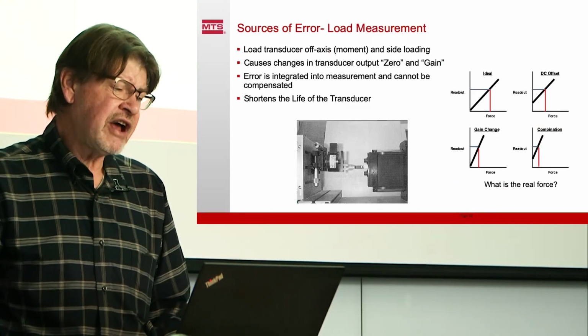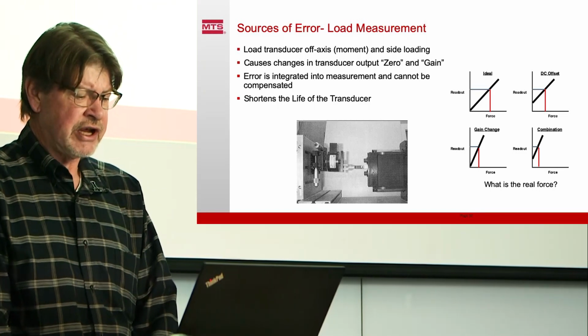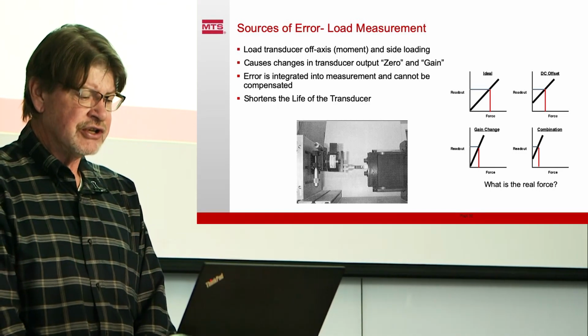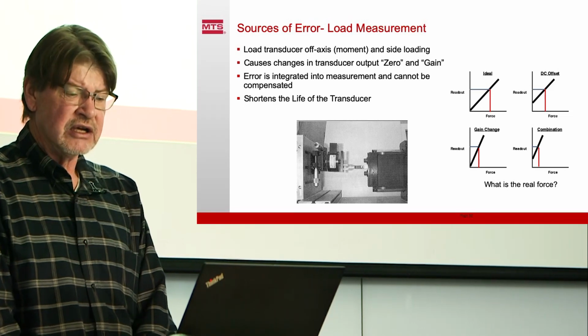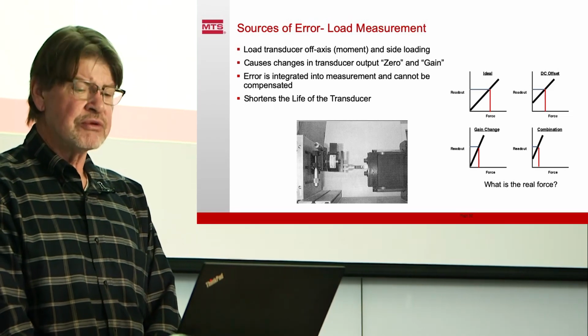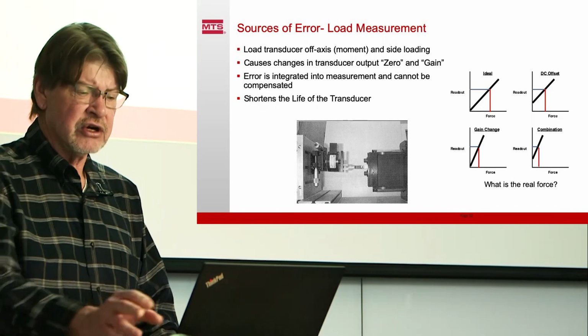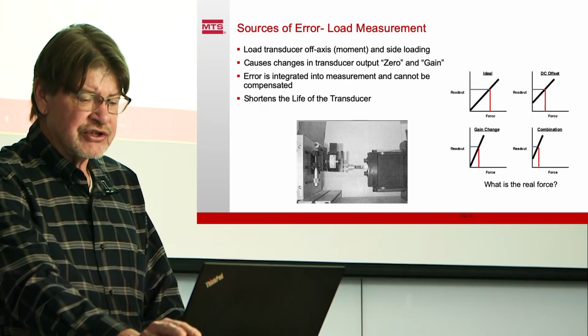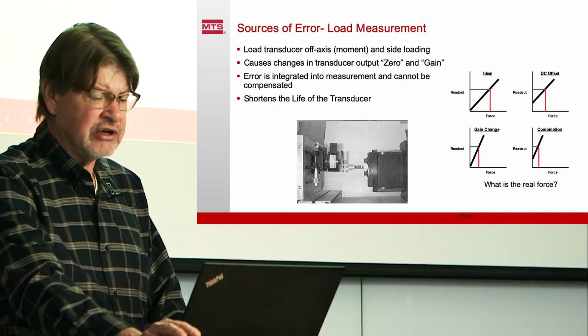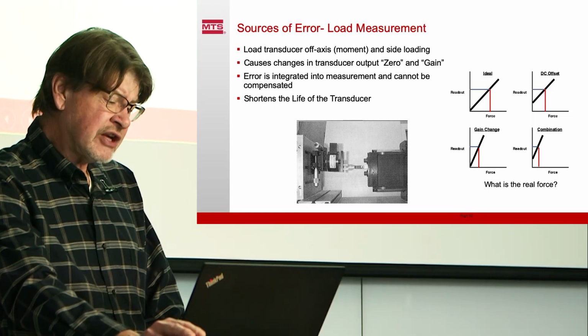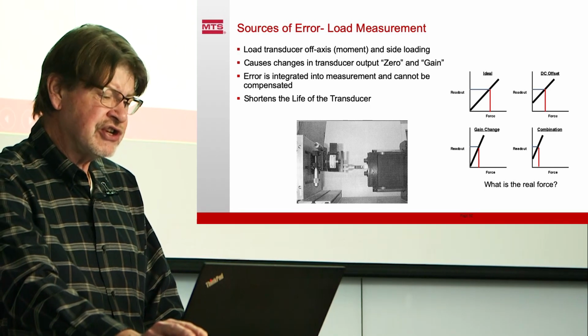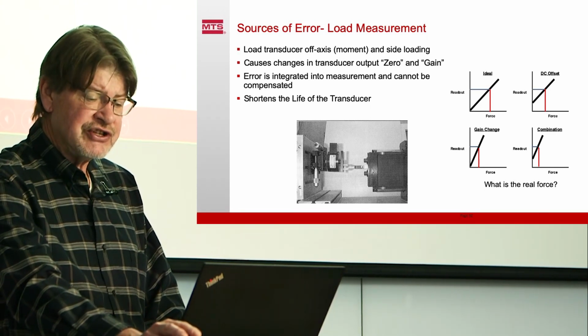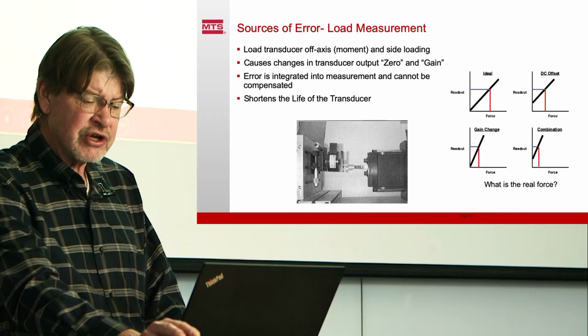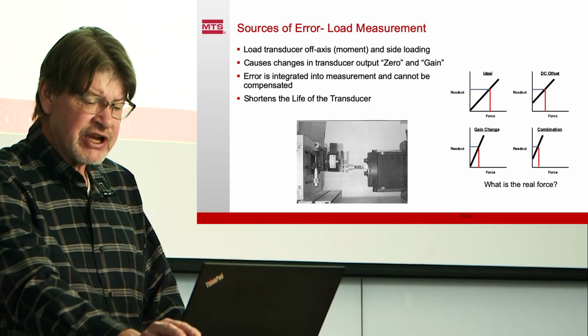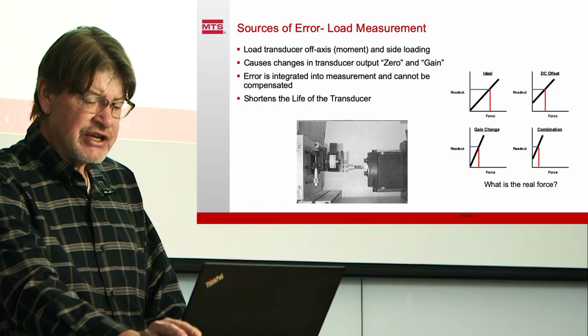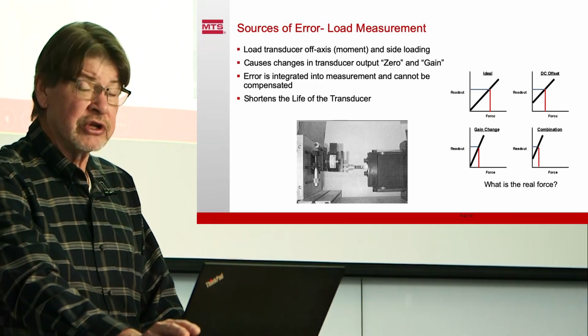What about off-axis loading? Nice little picture there. Side loading or moment loading a load cell. Is that going to give you the same output as loading straight on? Well, you don't know, and you don't know what the error would be. You look at the right over here, you see our gain curves. Ideally, we've got a readout that's very proportional to our force. Everything's linear and we like it. But then if we put an external load on this, such as an eccentric force here, we could shift the DC offset, we could shift the gain, or some combination of them, such that that same force input now gives us a different output. It can also shorten the life of the transducer.